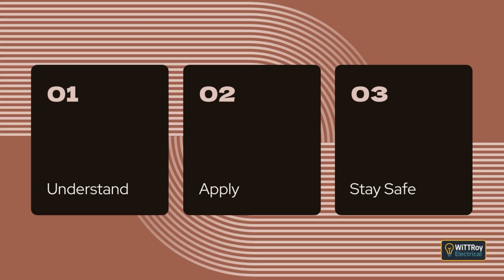Another example is double-insulated equipment, such as Class 2 tools or chargers. Even if one layer of insulation fails, the second layer maintains safety. PELV control circuits are another example, using low voltage that remains within safe limits even when referenced to earth. These methods give protection in normal operating conditions and during a single fault, which is why they are considered enhanced protection. Clause 1.5.4 Basic protection, protection against direct contact.